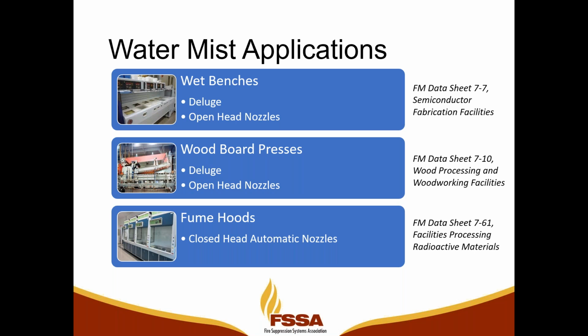We've also got wood board presses where we're taking wood dust or wood chips and manufacturing oriented strand board or particle board. And when we do that, we're working with synthetic resins and wood dust, or wood dust and paraffin or paraffin-like materials, all of which are obviously very flammable. We're also working with massive presses that push metal plates down to compress these particles together to make a board. And where we've got those presses, we've got hydraulics. So we've got hydraulic pits underneath these wood board presses, and they are very much subject to ruptured hydraulic hoses. So spray fires, pool fires, we test our systems to all of those when we want to get a wood board press approval. And again, there's some great diagrams in data sheet 7-10 that tell you how to protect wood board presses.